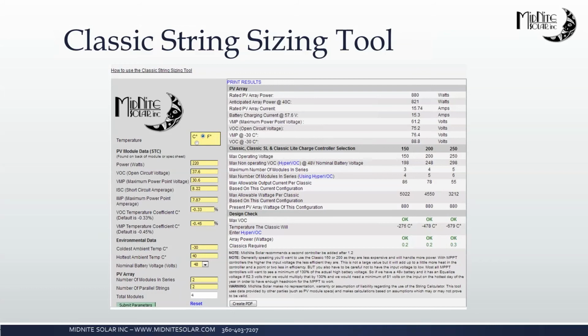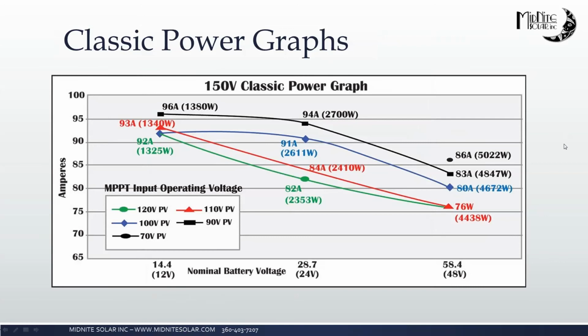So if you take the highest battery voltage you ever anticipate seeing, if you've got a 48 volt battery, we might say 60 volts. If we multiply that by 133%, that's going to be the PV voltage as a minimum that we're going to want to see. The string sizing tool will let you know if you're too low on your voltage, but that's just something also to be aware of. The high voltage can cause a little more heat in the unit, a little less efficiency, and you have to be above a minimum as well. Excellent point. Thank you, Ryan.